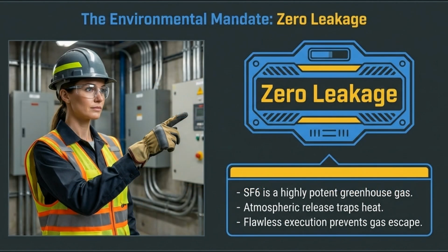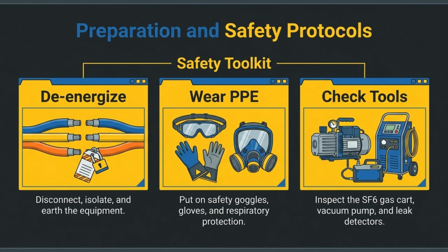Our environmental mandate is zero leakage. SF6 is a potent greenhouse gas, so flawless execution during filling prevents its atmospheric release, protecting our planet. Safety is paramount. Always de-energize and earth the equipment. Wear proper PPE, including respiratory protection, and check all tools, such as the SF6 gas cart and leak detectors.